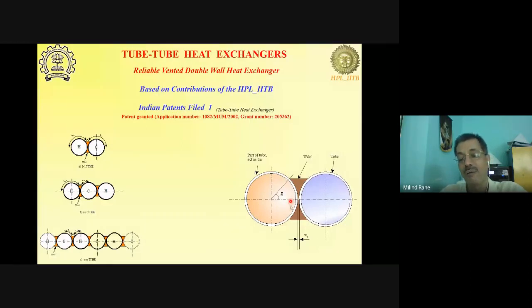For ammonia and seawater, like what we did in our shipboard chilling unit, we had ammonia passing through stainless steel tubes and seawater passing through cupronickel tubes. Now, conventionally, you would need a titanium heat exchanger to do that job if you were to use any of the conventional heat exchangers, whether it is plate type, shell and tube type, or tube in tube type, or things like that. But here you can get away with a lower cost cupronickel compared to titanium, and a much lower cost stainless steel or carbon steel on the ammonia side. So that is the beauty of these heat exchangers.